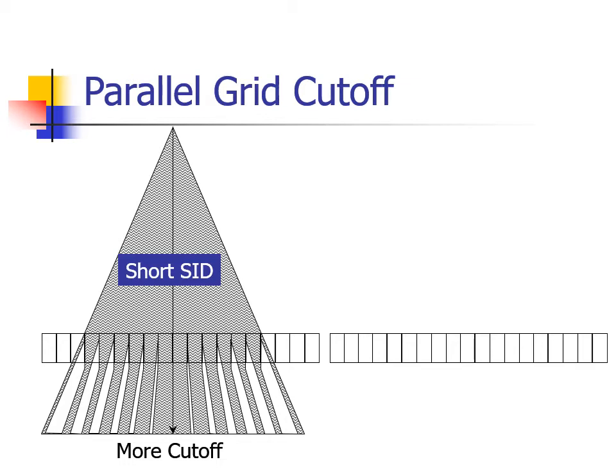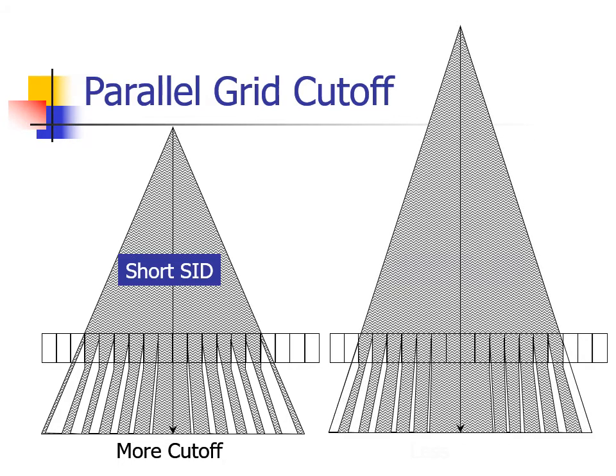Cutoff is more pronounced in high ratio grids. Notice that if one increases the source to image distance, cutoff becomes less severe. This is because at a longer distance, you use rays that are more from the center of the beam, and these rays diverge less. They are closer to perpendicular to the grid.